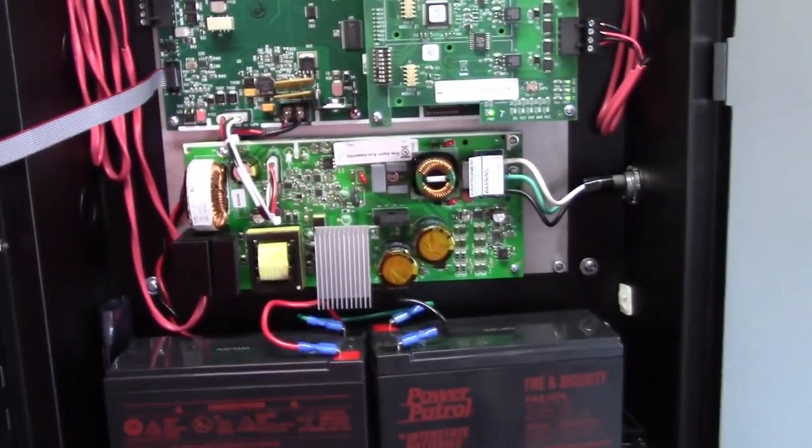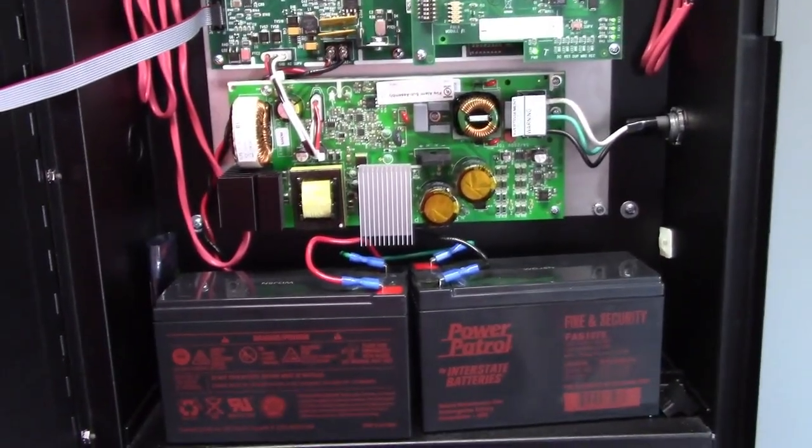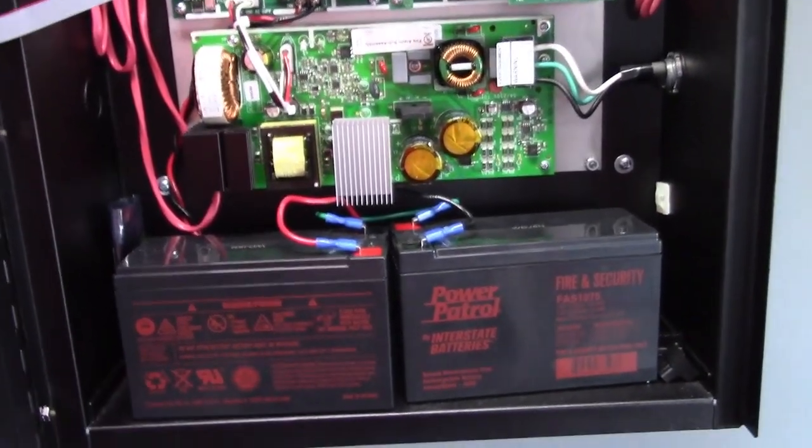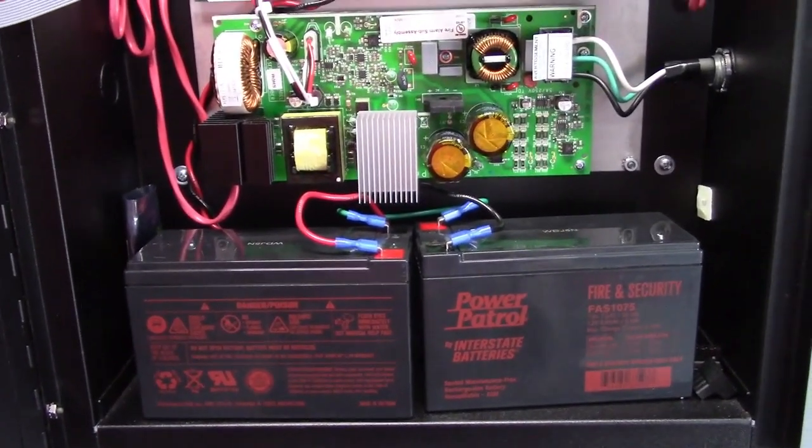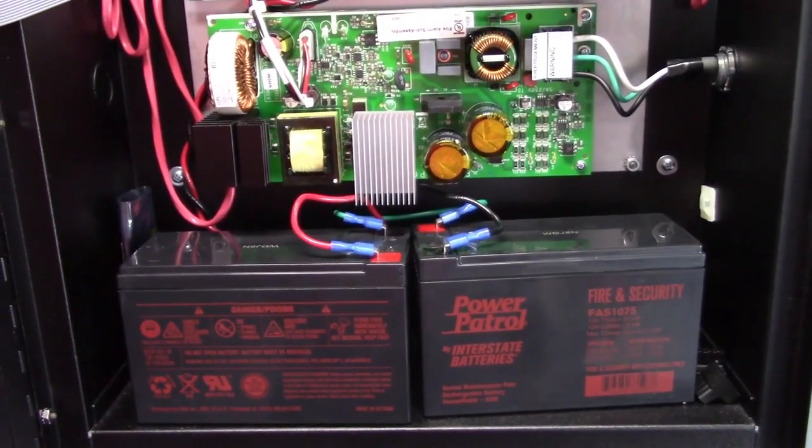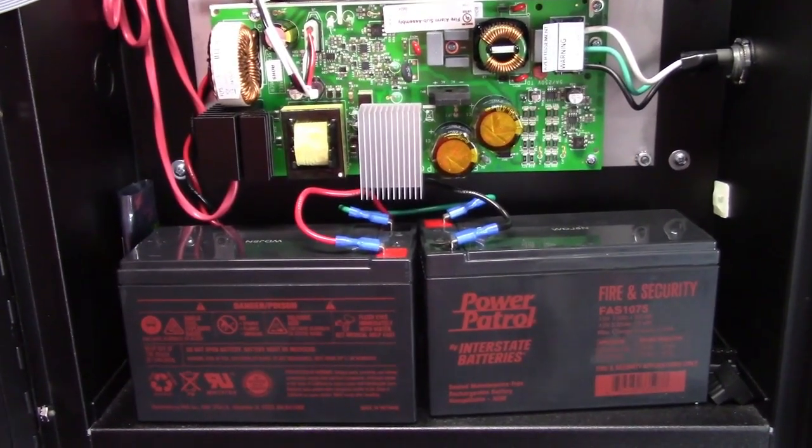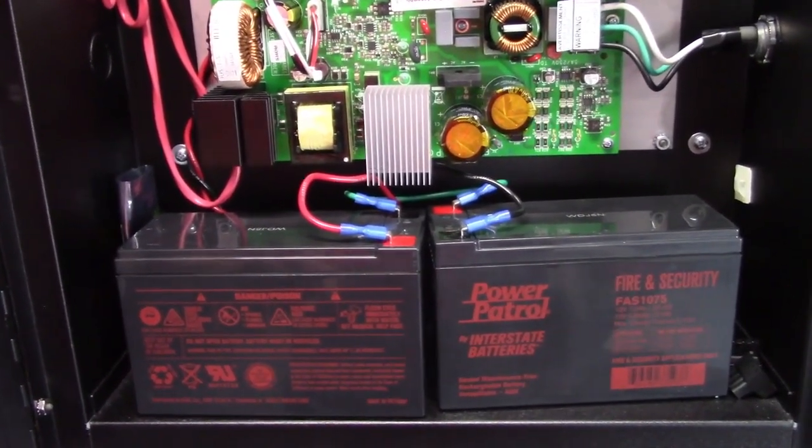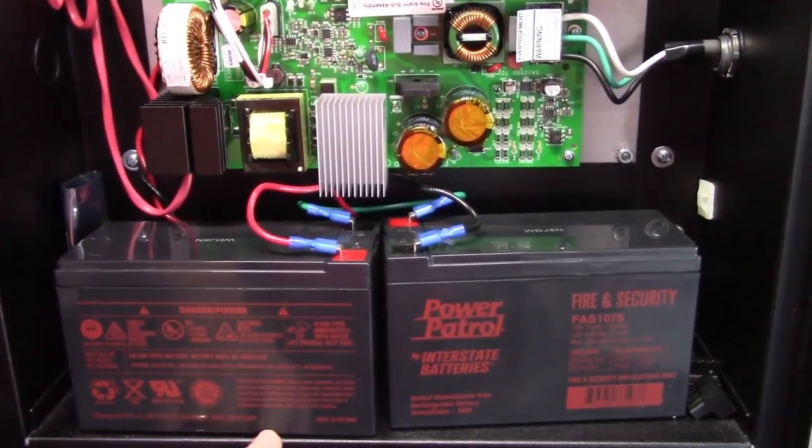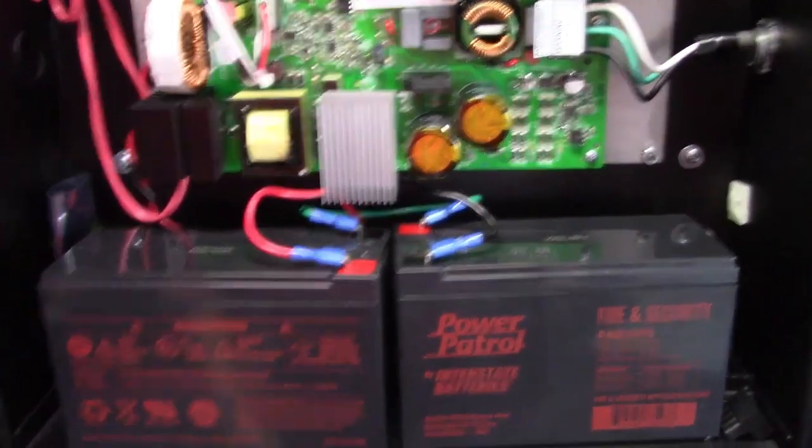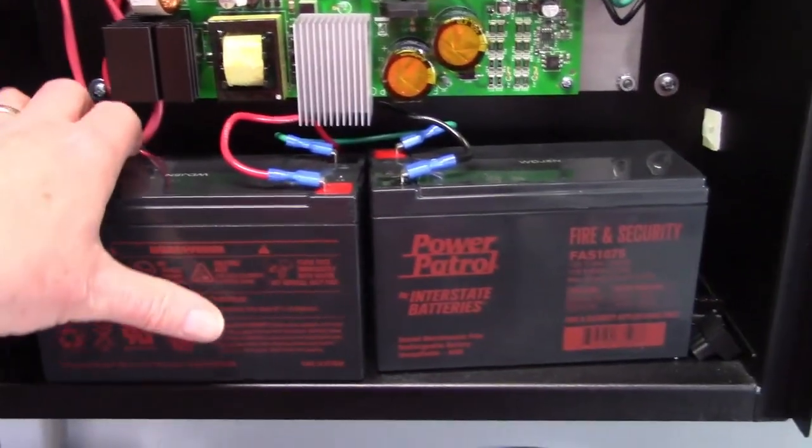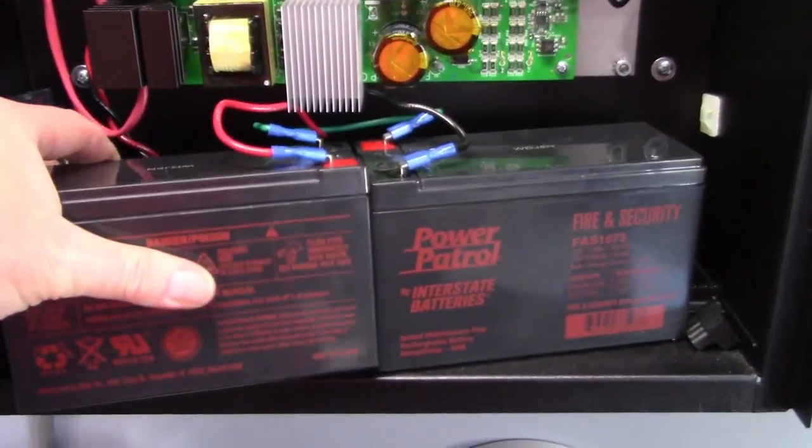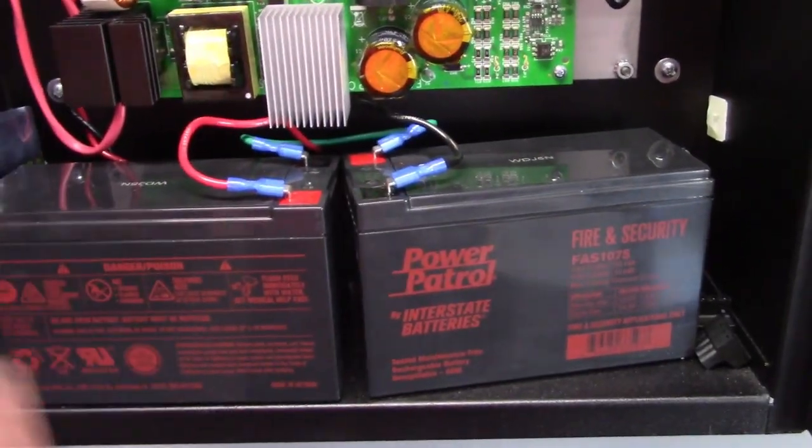Lastly, this is rare, but it can happen. The bottom side of a battery can get damaged, and it could be metal to metal contact on the bottom of the fire alarm panel. Usually that can be determined by lifting the batteries and inspecting the bottom.